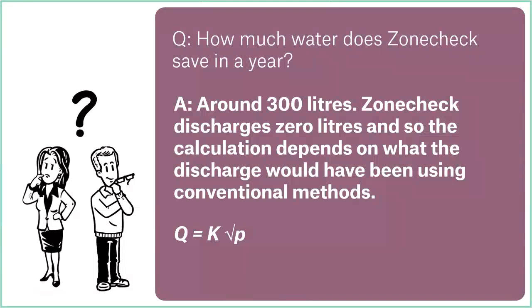And obviously the test has to be completed at least 4 times a year. So we can times that up. We can do 320 times 4, which is 1,280 litres. And obviously that will also be multiplied by the number of flow switches or number of zones that you have in the installation. So yeah, it can add up to a very large quantity of water very quickly. So that's how zone check saves water.